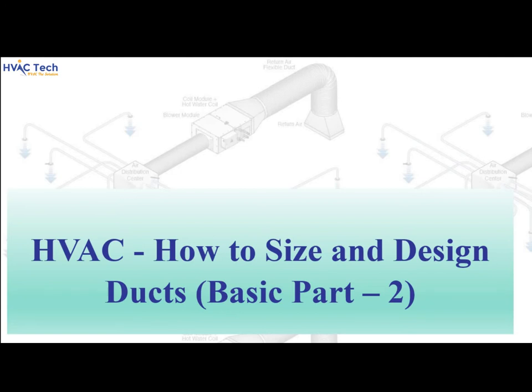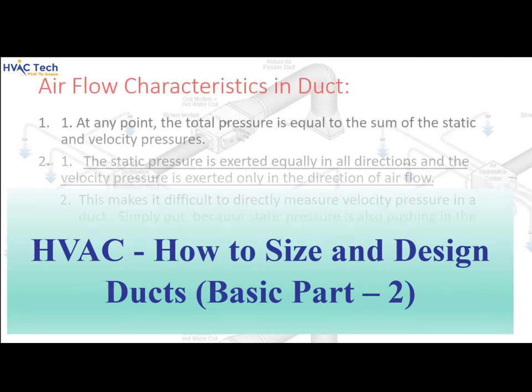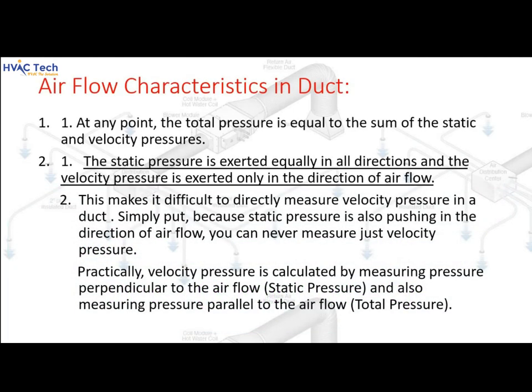HVAC: how to size and design ducts, basic part 2. Airflow characteristics in ducts: at any point, the total pressure is equal to the sum of the static and velocity pressures. Static pressure is exerted equally in all directions, while velocity pressure is exerted only in the direction of airflow. This makes it difficult to directly measure velocity pressure in a duct, because static pressure is also pushing in the direction of airflow.